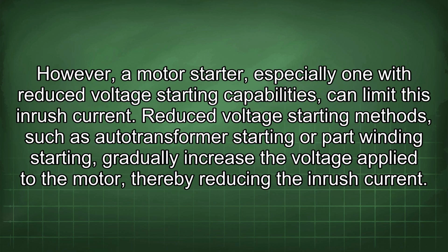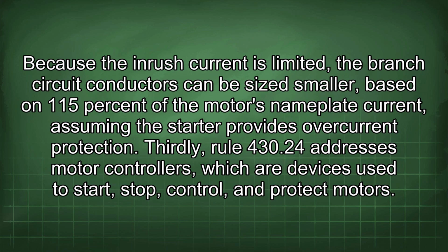However, a motor starter, especially one with reduced voltage starting capabilities, can limit this inrush current. Reduced voltage starting methods such as auto-transformer starting or part winding starting gradually increase the voltage applied to the motor, thereby reducing the inrush current. Because the inrush current is limited, the branch circuit conductors can be sized smaller, based on 115% of the motor's nameplate current, assuming the starter provides overcurrent protection.